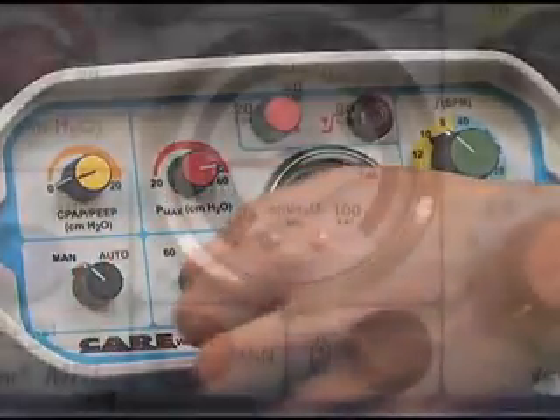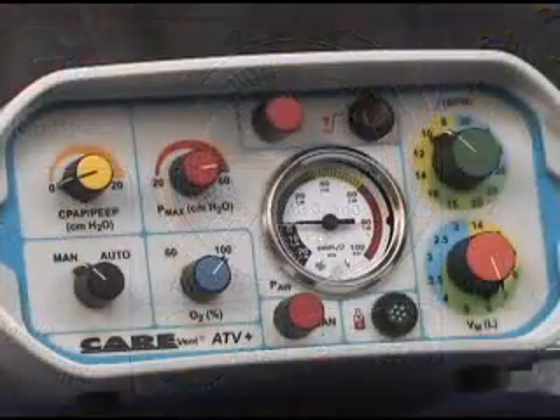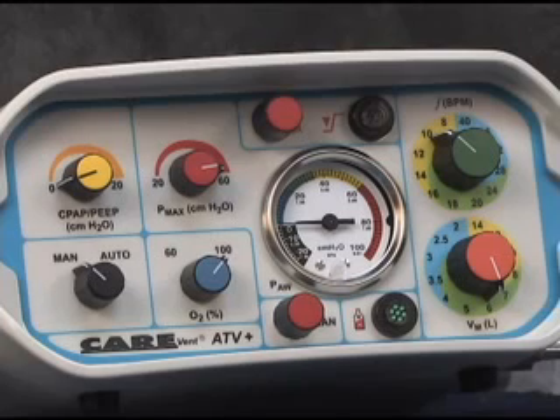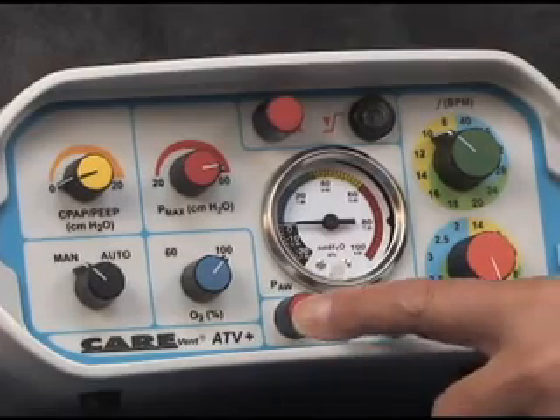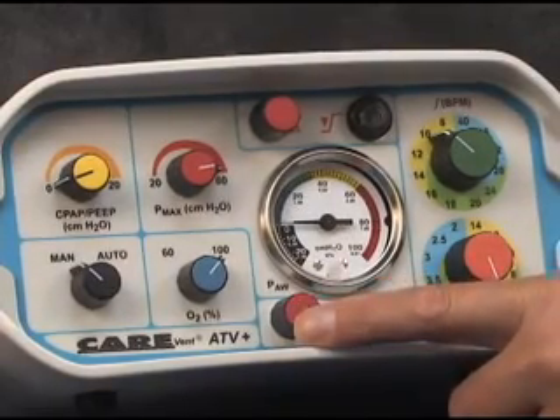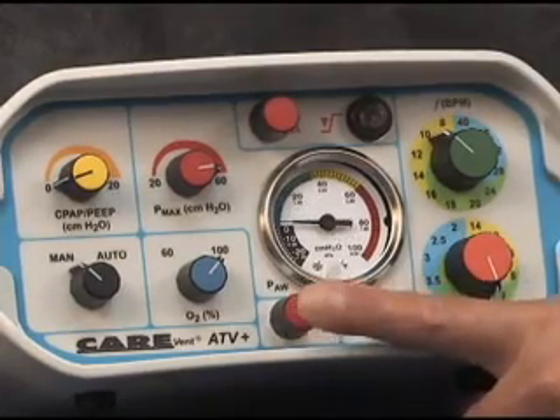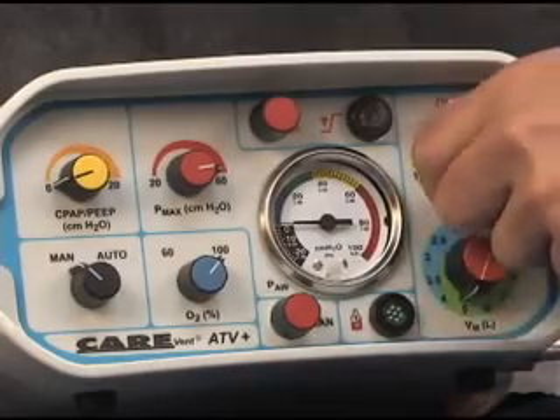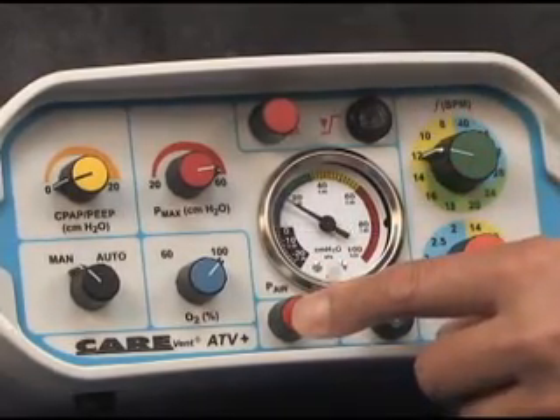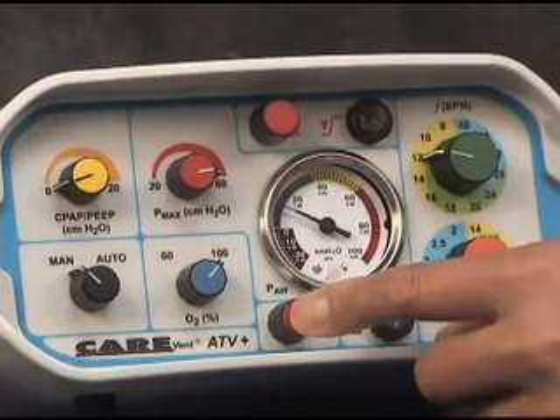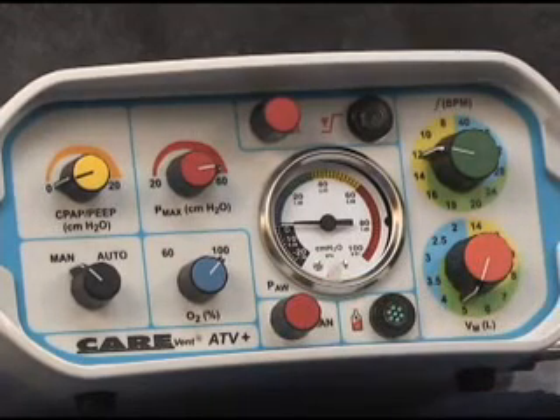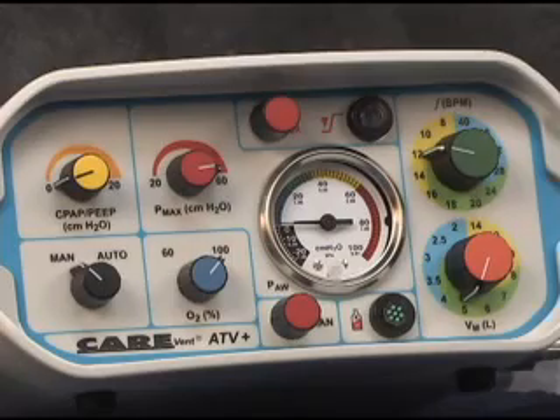The manual or automatic control selector, when in the man position, allows the gas supply to be turned on, making the ventilator ready for any breathing emergency. In the manual position, the manually activated manual ventilation override button will provide manually triggered assisted ventilations to patients who are experiencing distressed breathing or to provide ventilations to a non-breathing patient. The flow rate is equivalent to the minute volume flow setting selected, providing flow rates equivalent to the size of the patient being ventilated. This reduces the peak airway pressures generated and, in the mask-ventilated patient, significantly reduces the potential for gastric insufflation and associated risk of aspiration of stomach contents.